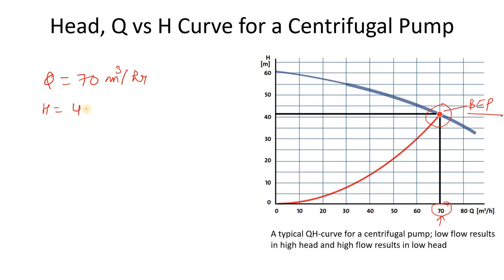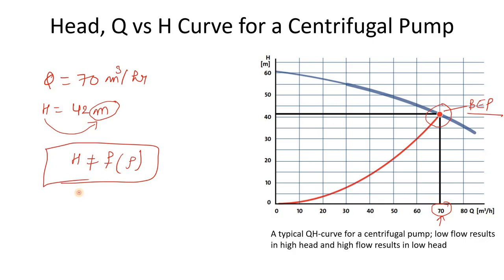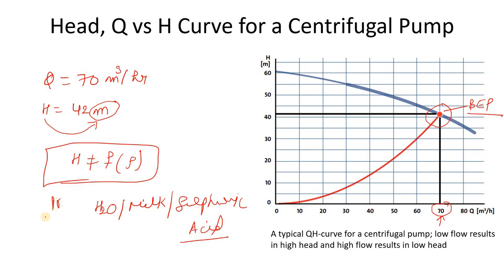The head unit is measured in meters. We use head rather than pressure in the pump curve because head is not a function of density — it means it doesn't matter whether you use that pump for water, milk, or sulfuric acid; the head remains constant. We cannot use pressure here because pressure changes with fluid density. That's why we provide the head versus flow rate curve.